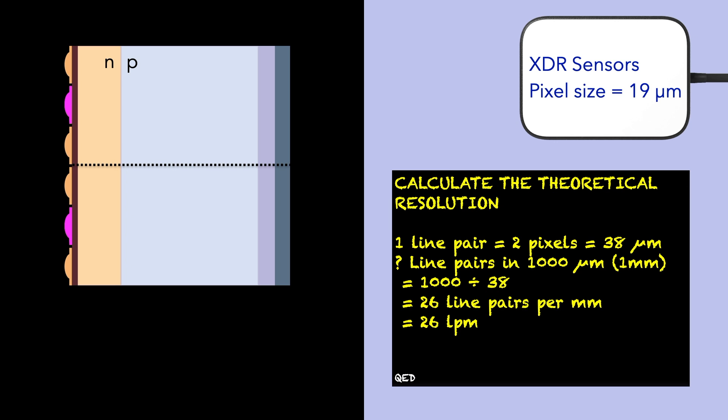The pixel size of a sensor is an important consideration. Using the pixel size, you can calculate the resolution of an image that you can expect to see. A higher resolution image provides more detail. Using the pixel size, you can calculate the theoretical resolution of the image from an XDR sensor, and this is 26 line pairs per millimeter.